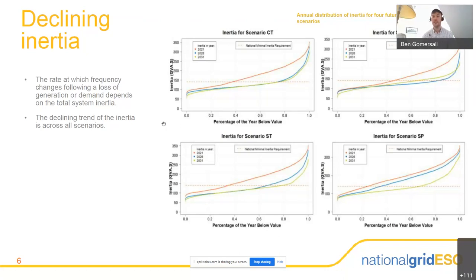Inertia minimum of about 100 GVA seconds, driven by trying to keep the rate of change of frequency down to about half a hertz per second for a largest loss of about 1800 megawatts. If you use the swing equation that the previous speaker spoke about, you get a limit of around 90 GVA seconds that would contain that. However, when you see that large loss in the system, it's also associated with an inertia loss, which is something you need to consider. So when you're losing the megawatts, you're also losing some inertia associated with it. So we obviously need to keep it a little bit higher, such that post the loss of that unit, we're still above that 90 GVA seconds limit.